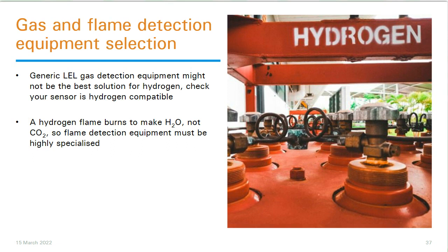And a lot of flame detection equipment looks for soot particles or looks for IR signature from CO2. If those soot and CO2 are not present in the hydrogen flame, if we're just looking for water vapor and heat, then we need to have a flame detection system that is working in a very, very different way, in a very, very specialized way.